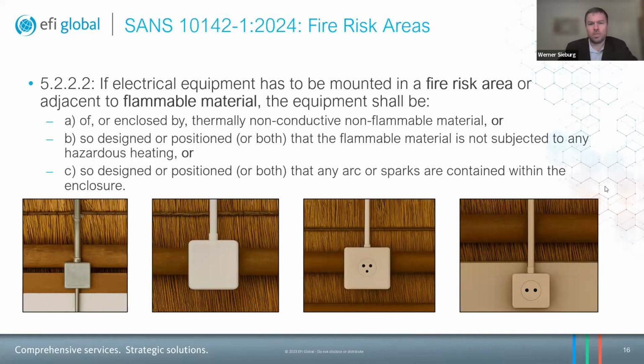Right. Then the second box, and in many instances, these electrical boxes are of flammable material. They are enclosed, yes. So oxygen flow to the point of electrical failure or to the point of ignition of a fire is very often limited. But once the plastic casing of such boxes melts and additional oxygen is added, and if in such conditions the electrical fault persists, then the mounting position of these boxes becomes very critical. So there are obviously non-flammable, non-conductive fiber type boxes that you can install in these kinds of circumstances.